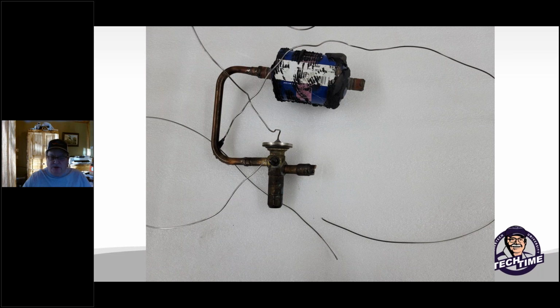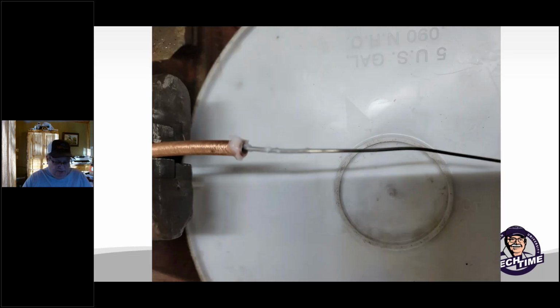So again, we want you to score the stainless steel line, and you're going to break it in half like we showed before. You cannot fix and repair the power head one because that's got a special gas charge in it, so it doesn't pay to try to fix that. That's when you'll need to replace your expansion valve. Similar type of repair: as you can see, I've cleaned up the stainless steel tube, run flux around a piece of copper, and I'm going to crimp it in tight, and then add more flux around it again.